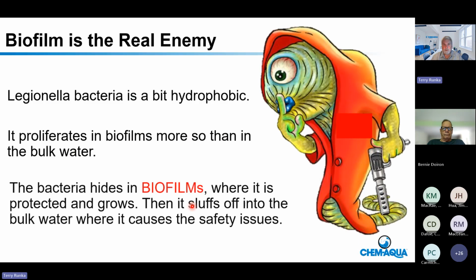Now, here's the real secret. Let's talk about biofilm. I've mentioned it a few times. Legionella is a bit hydrophobic. It does not really like to swim around in the bulk water that's in the cooling towers and in the hot water distribution loops. It loves to hide in biofilms, where it's protected inside the biofilm from all the things that we can do to it. And it grows inside the biofilm and then sloughs off. And that's when it becomes a safety issue. It's safe as long as it's in the biofilm.